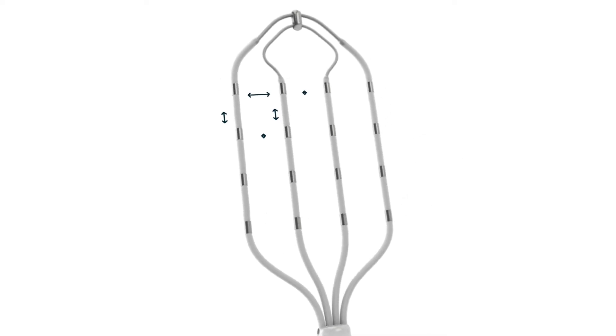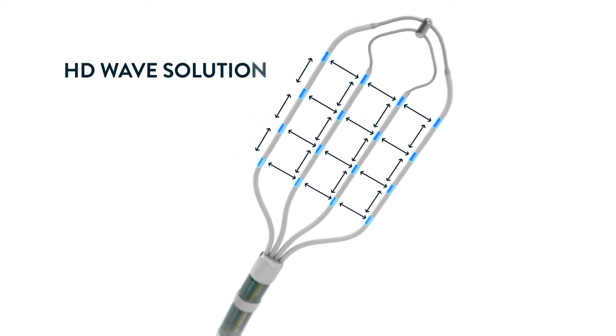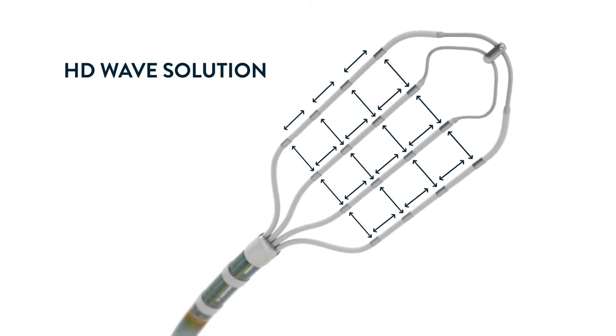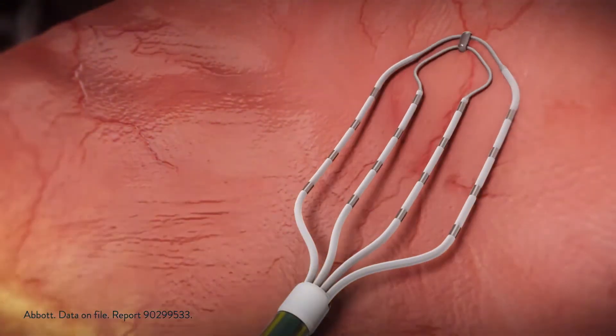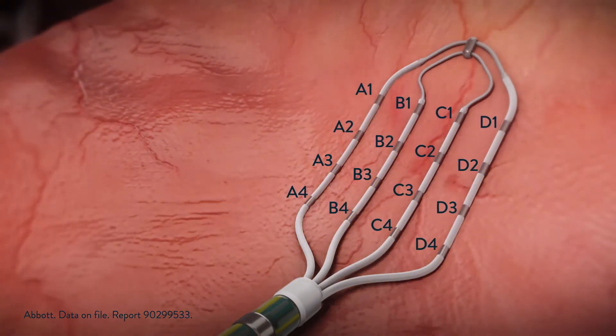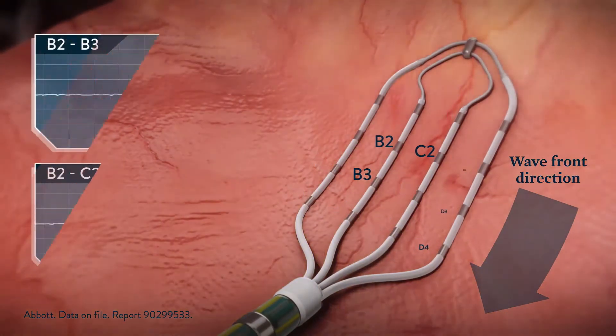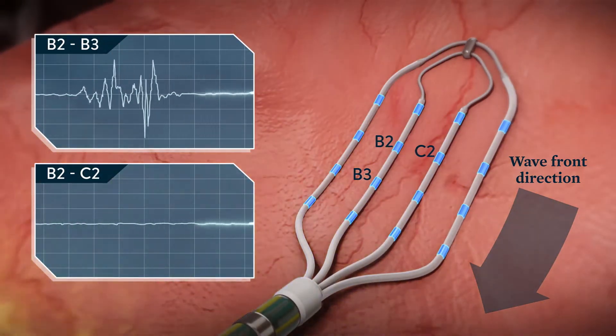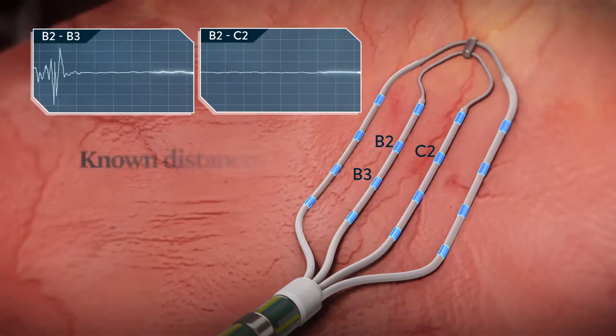To overcome poor orientation to the wavefront, the Advisor HD Grid Mapping Catheter, Sensor Enabled, has equidistant spacing, allowing an HD wave bipole recording along and across the splines. The unique grid design of 16 electrodes allows for rapid data collection from multiple bipolar combinations in a given location. HD wave selects the highest amplitude electrogram from two orthogonal bipoles, reducing directional sensitivity.